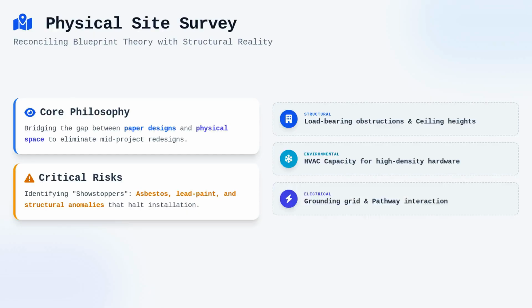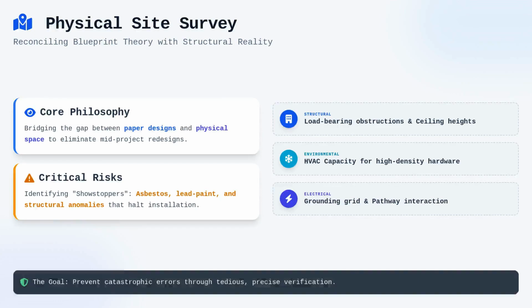You need to investigate the existing HVAC capacity in telecommunication spaces, because a room designed for legacy equipment often lacks the cooling for modern high-density hardware. Furthermore, verify the existing grounding grid to ensure that any proposed pathways will not interact negatively with current electrical installations. This phase of the project is often quiet and tedious, but it is precisely where you prevent the catastrophic errors that lead to mid-project redesigns.